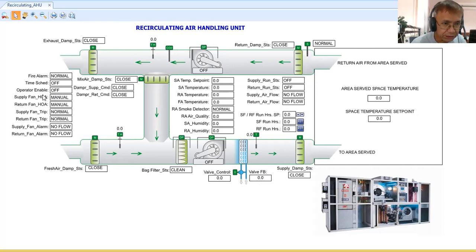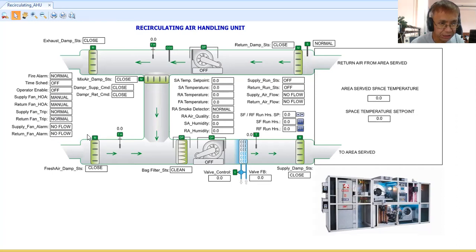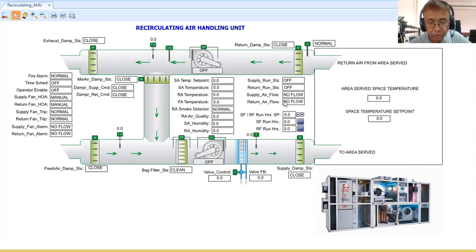For example, if maintenance personnel need the AHU stopped, they can call the BMS room and ask the operator to disable the AHU. The monitoring points for supply and return fans include hand-off-auto, fan alarm, and airflow alarm — these software points and alarms are generated in the control logic program.